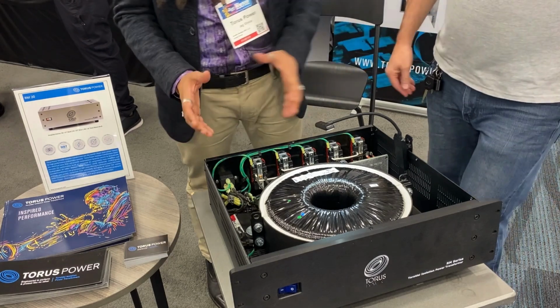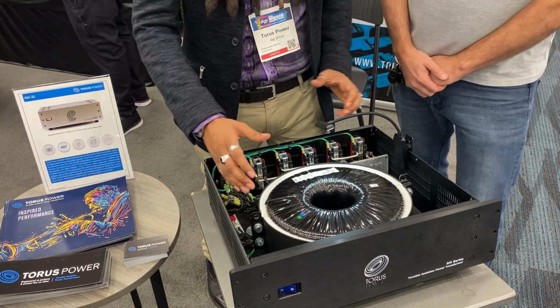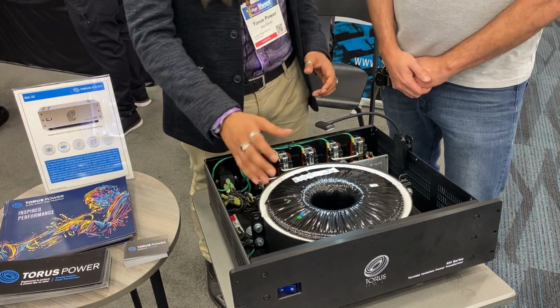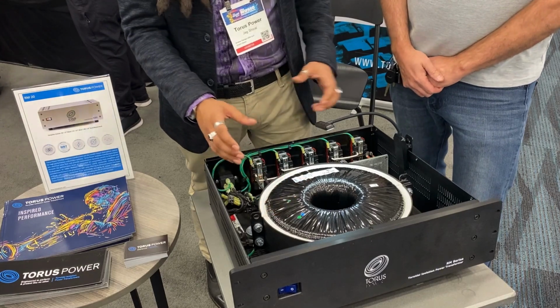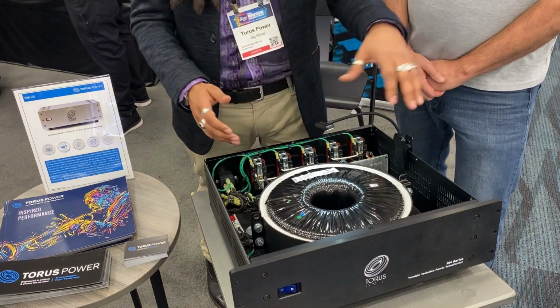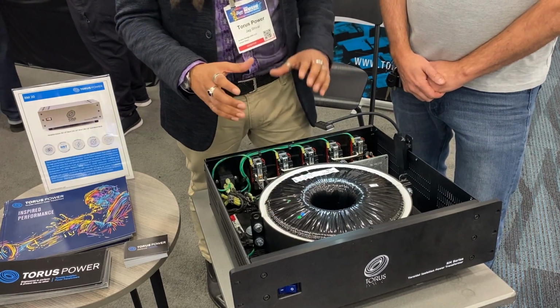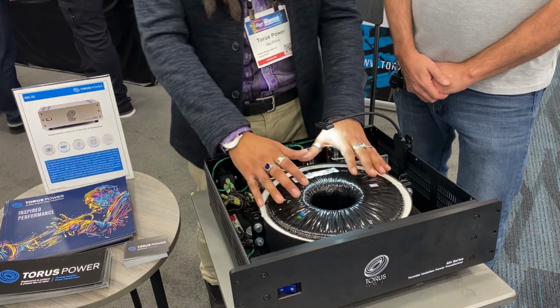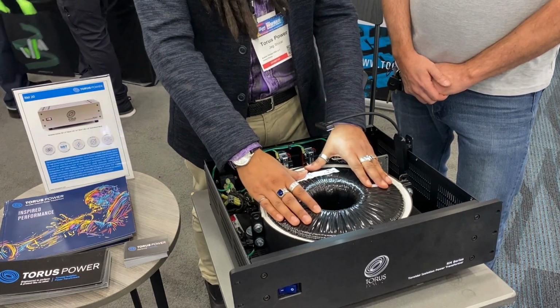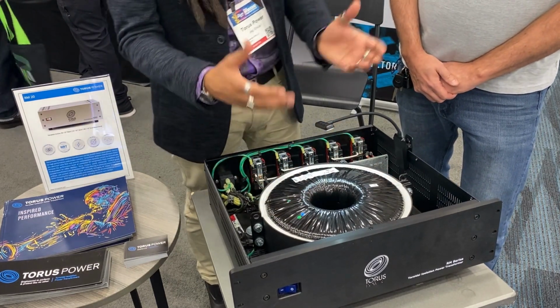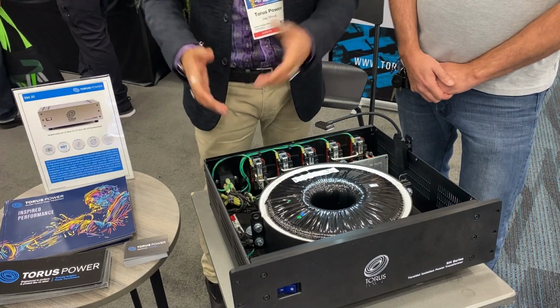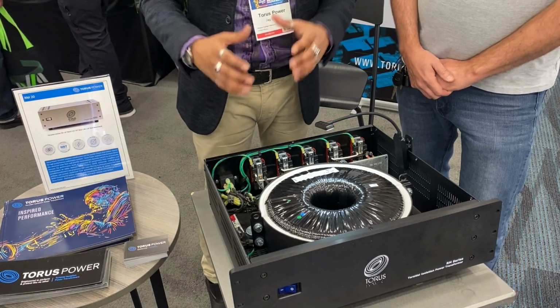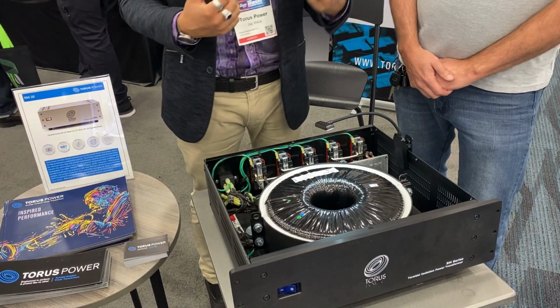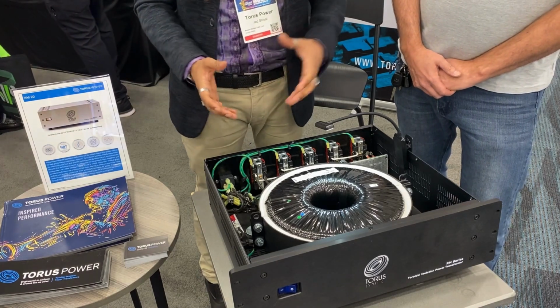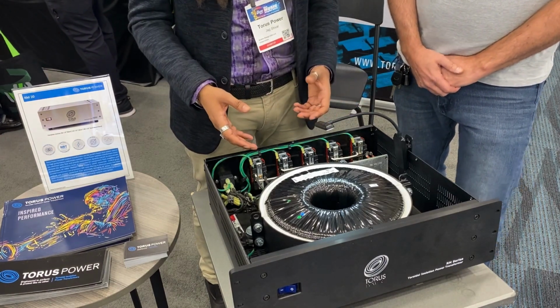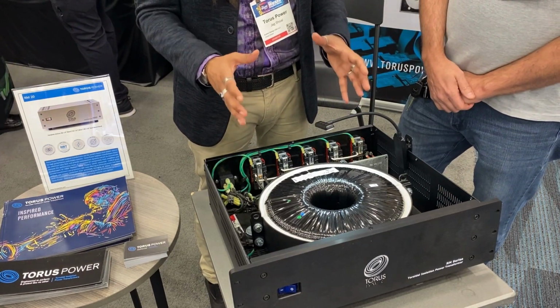The basics of it is you have the incoming power coming into and wrapping around the toroidal transformer, and that's called a primary winding. Then that's insulated, and you've got the secondary winding over top of that. That primary winding creates a magnetic field within this large toroidal transformer, which is picked up by induction into the secondary winding, which then feeds your equipment. So it's important to know that there is no physical connection between your input and output - what's being transferred into your equipment is just a pure AC sine wave.